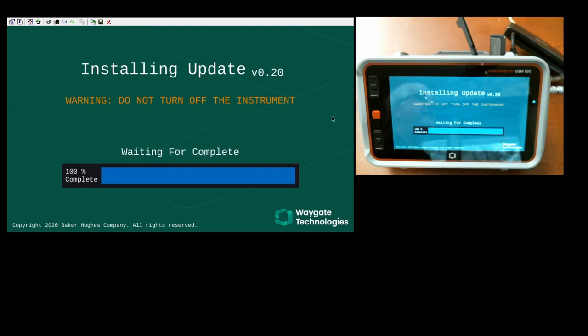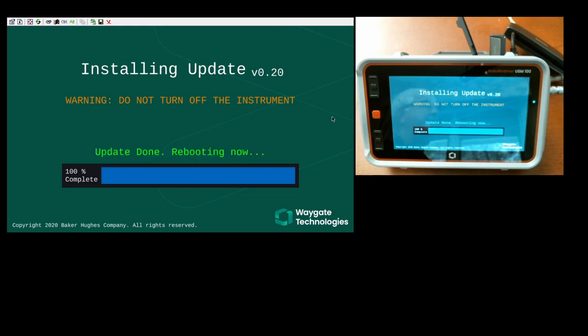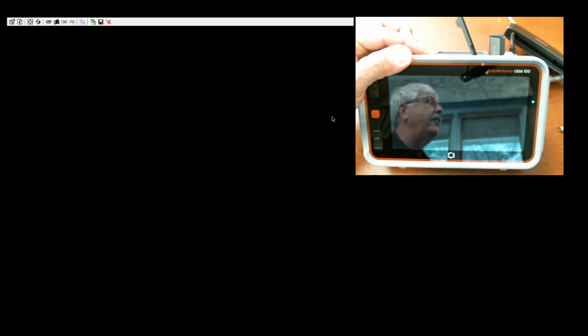Okay, at the very end of the process, the instrument will appear to turn off. So we'll see the update window go away as we lose our connection as the computer begins shutting down. Now, unfortunately, there's a small bug at this point in the process right now. And the instrument has not turned all the way off. If you notice, the LED is still lit over here. Even if I unplug the charger at this point, the LED is still lit. So what I'm going to do is do a forced power down. I'm going to reach up to the top here. I'm going to press the power button. I'm going to hold that for 10 to 15 seconds. And at some point in that 10 or 15 seconds, we see the LED turn off. We'll hear the click. And at that point, we can go ahead and reboot the instrument with the normal power on sequence.